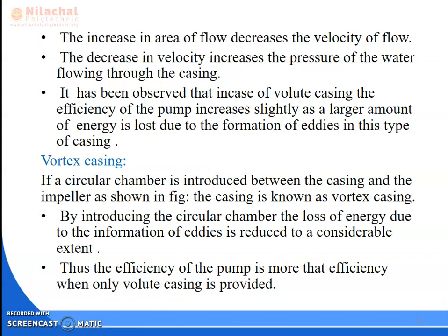The increase in the area of the flow will decrease the velocity. If the velocity decreases, then it will increase the pressure of the water flowing through the casing. That's why from the inlet to the outlet, the pressure energy will increase. Okay. It has been observed that in the volute casing, some of the energy will be lost due to formation of eddies.